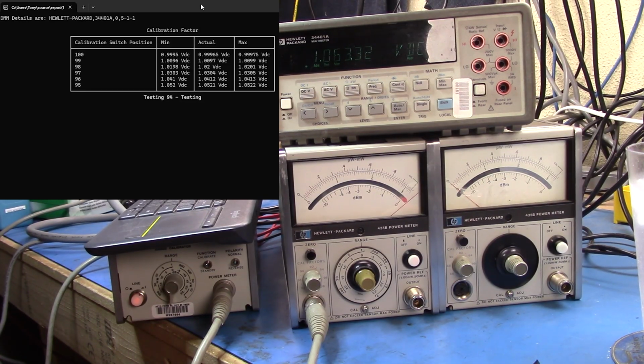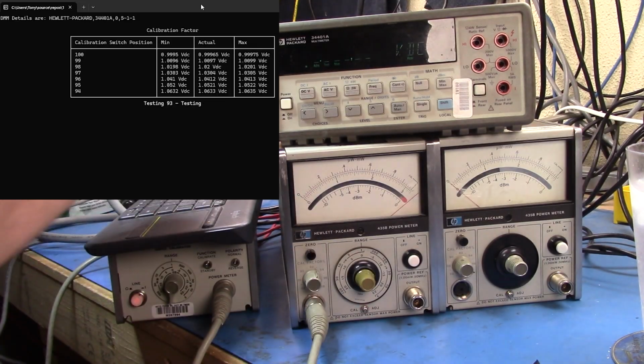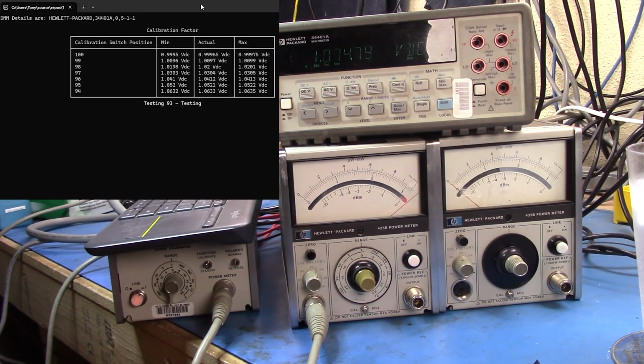For a more advanced meter like the 437B, you can actually program a set of the complete data for a sensor into the meter itself. So then all you need to do is select the sensor and then tell it what frequency you're measuring at. They didn't have that functionality in the 438A, I think. Not sure why they didn't do that. And then, as I said, in the later sensors and meters, it's in non-volatile memory on the sensor itself. So you just plug it in, it syncs up, it reads in its calibration factor table, and then you just tell it what frequency you're measuring, and Bob's your uncle. Anyway, that's why the calibration factor exists on the meter.